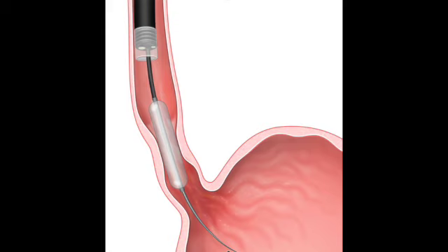Standard balloons are what we call compliant. You push air or water into them, and they just keep stretching and expanding in all directions until they burst. Right. A controlled radial expansion balloon is non-compliant or semi-compliant. It is made of specialized polymers designed to expand to a very specific, predetermined diameter based on the exact amount of pressure applied. So a single balloon catheter can be stepped up to multiple highly accurate sizes. Yes, up to 3 different sizes usually.